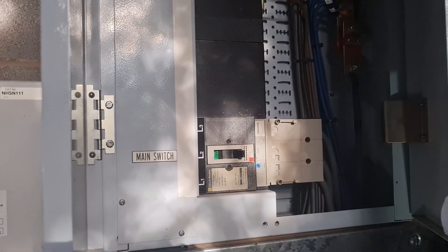We're going to run through some tests in here as well — insulation resistance tests to make sure we've got no dead shorts anywhere in the cabling, and check that all of the phase and neutral voltages are correct and present. Then we'll get the meter swapped over to a nice new three-phase meter. Matthew's down in unit 20 to make sure the wiring inside there's all fine. I'm pretty confident it's just an issue with this particular meter. The site maintenance guys have come out and refused to re-energize anything, which is the right call.